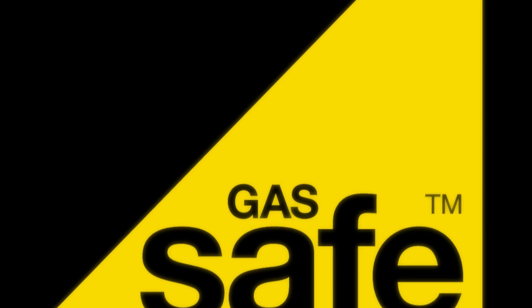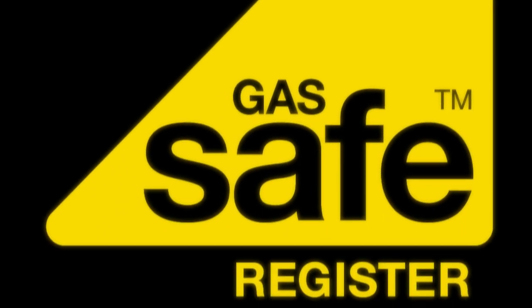Thirdly, it is possible to use a solar thermal system with a combi boiler. You can preheat the water that passes into your combi boiler using solar thermal. You'll need space for a small storage tank in order for this to work. So if you installed a combi because there was no space for a tank, this may be a problem. In addition, not all combi boilers are suitable. It must be fully modulating and designed to be able to take hot water in the inlet. A GasSafe registered engineer can verify this for you.